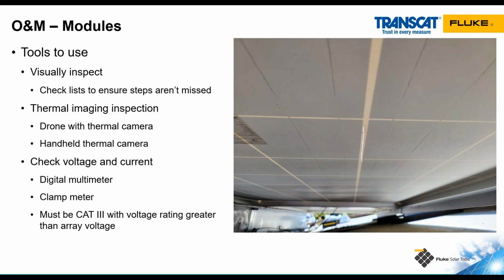Whatever meter we're using to test voltage, especially in a PV system, we need to make sure it has a category 3 voltage rating higher than whatever testing I'm going to be doing. So if I'm on a residential system, I need to have a 600 volt meter. If I'm on commercial rooftop systems, I can have a 1000 volt meter. And if I'm on utility scale projects, you're most likely going to need a 1500 volt meter.